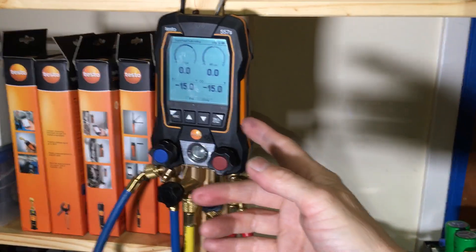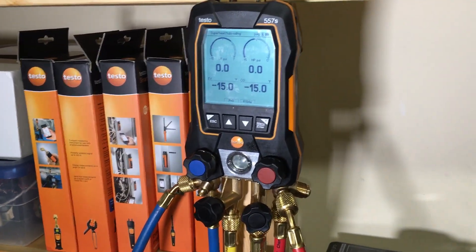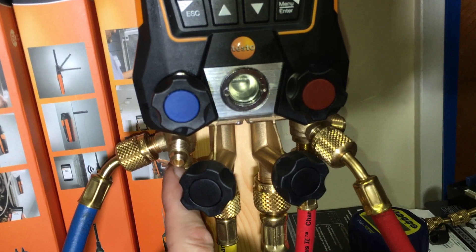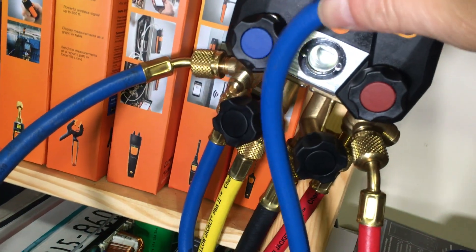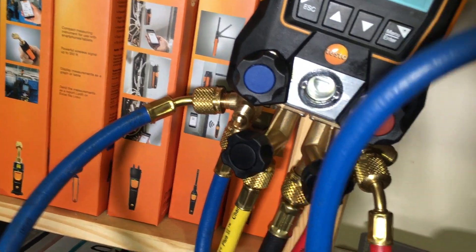I'll get my ultrasonic leak tester and pressurize this up with about 460 PSI of nitrogen again. Then I'll go along the hose at the ferrules and around the fittings where the seals are. Hoses have little tiny holes — sometimes manufacturers make them big enough for your eye to see, and sometimes they don't. That's what I'm trying to catch here in the light.